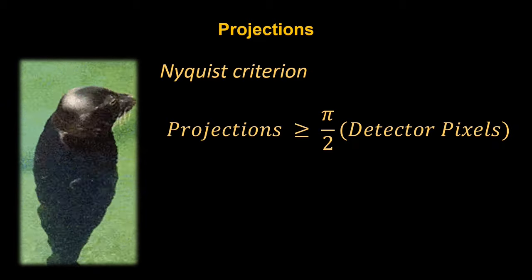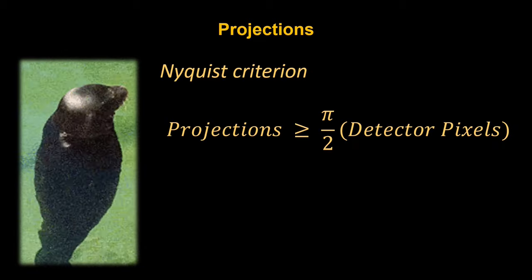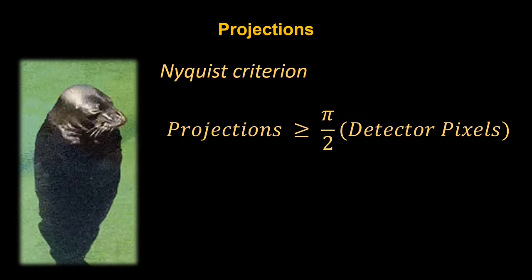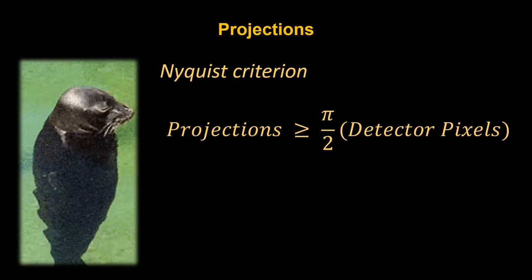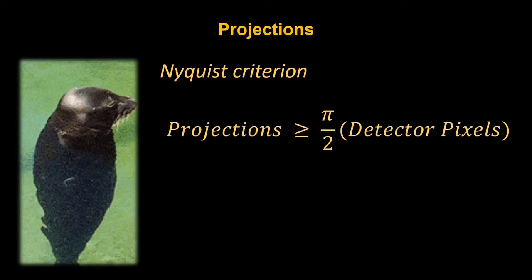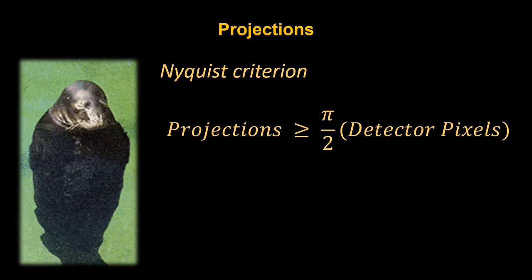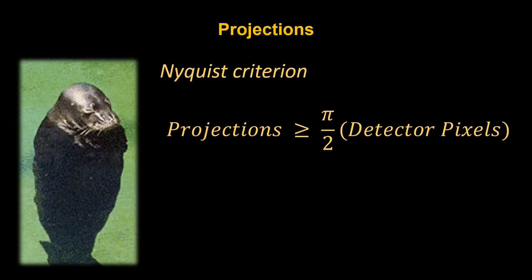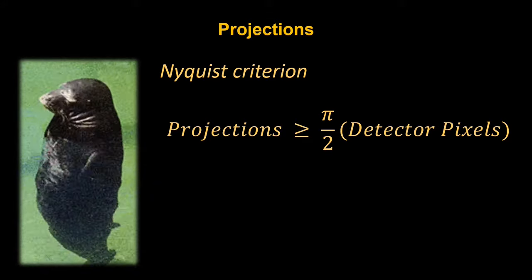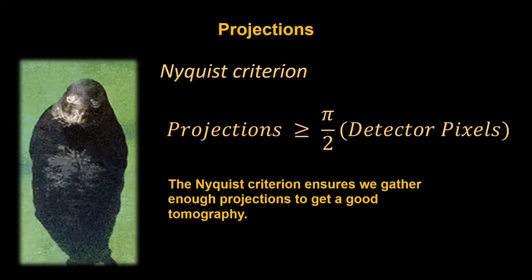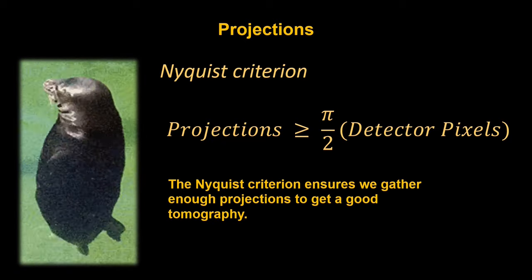And for that, I have another rule of thumb, the Nyquist criterion. The Nyquist criterion describes a relationship between the detector size and the amount of projections that we have to gather. The Nyquist criterion states that the number of projections we gather should be greater than or equal to π/2 multiplied by the detector pixels in the horizontal direction. For the Nikon, this is about 2,000 pixels that we multiply by π/2, giving us 1,000 multiplied by π, which would be 3,141 projections that we would gather to get an optimized tomography.